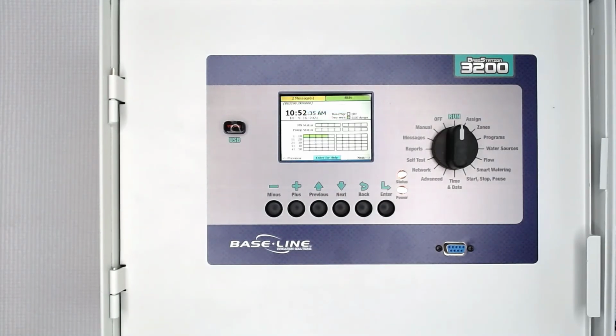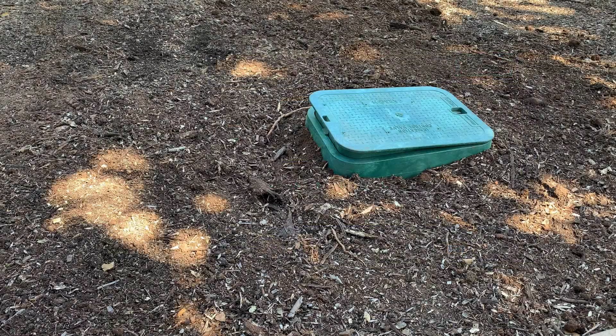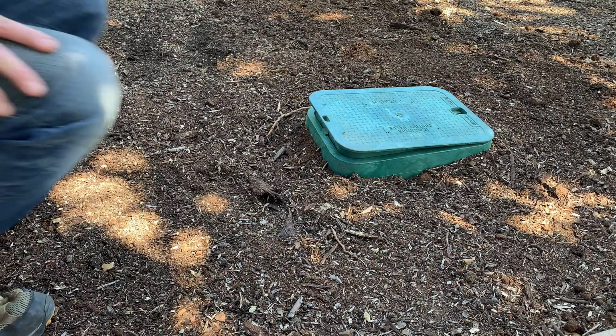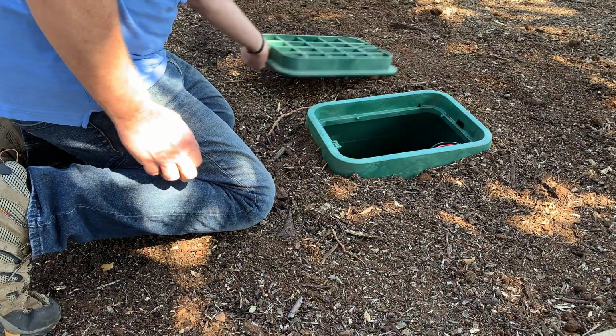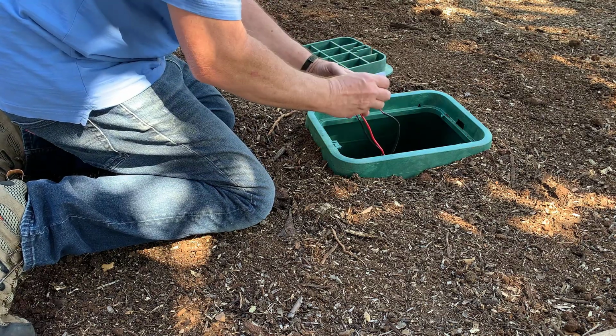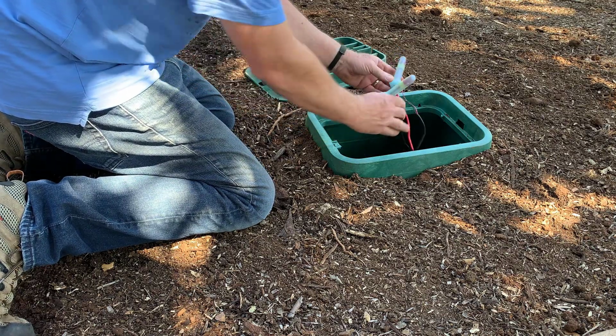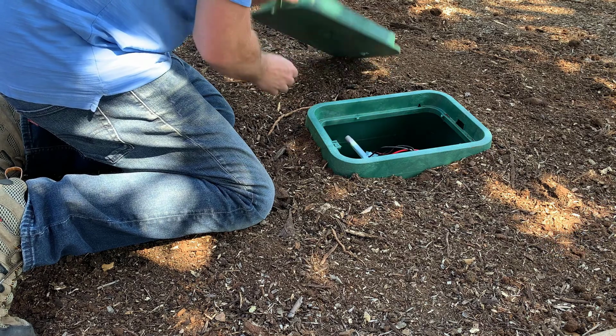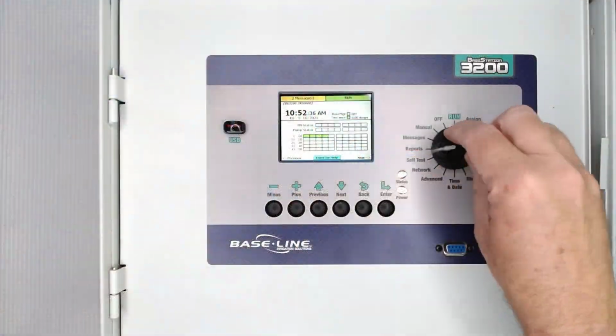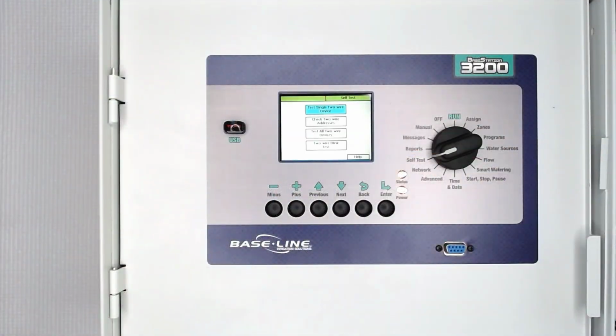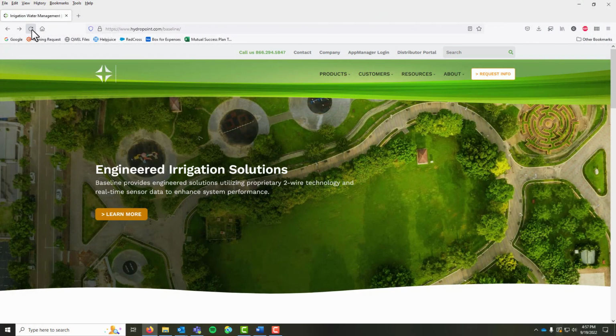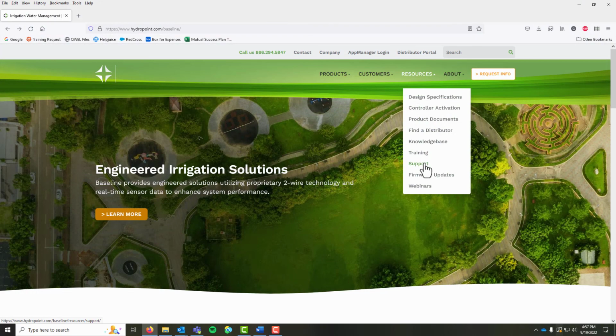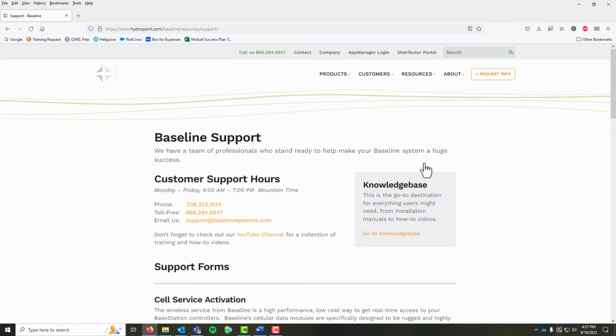If the controller can communicate with the sensor while directly connected to the controller, we eliminate the device as the issue. This means the problem is either on the wire path or the splices on the wire path. Ready for some troubleshooting? Look closely at wire splices, wire integrity, or for wire damage. If the controller couldn't communicate with the sensor while it was connected to the controller, the sensor is likely the issue. Contact baseline support via email or phone to see if your device is eligible for warranty replacement.